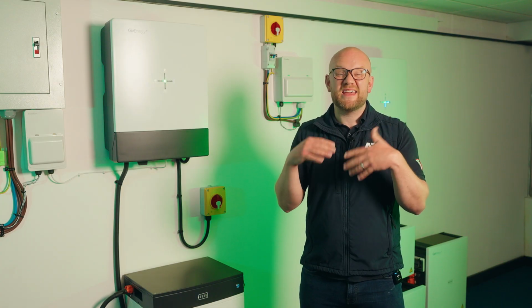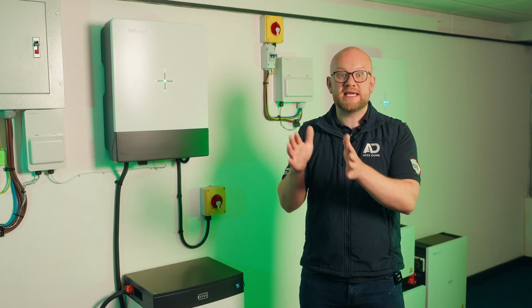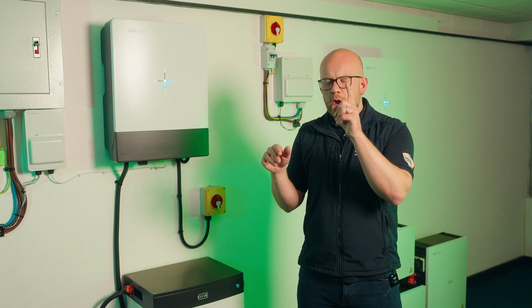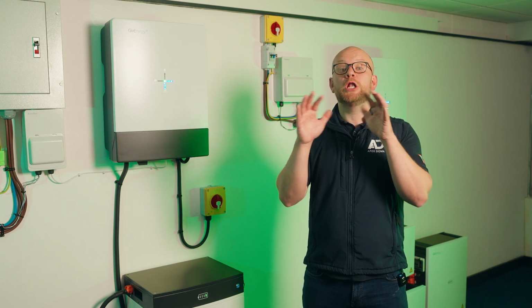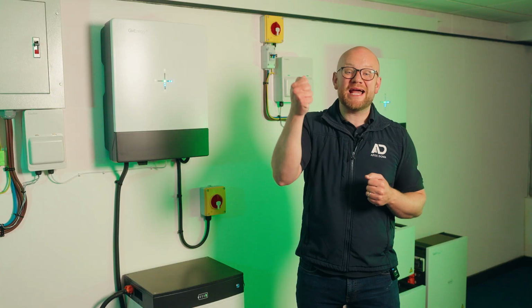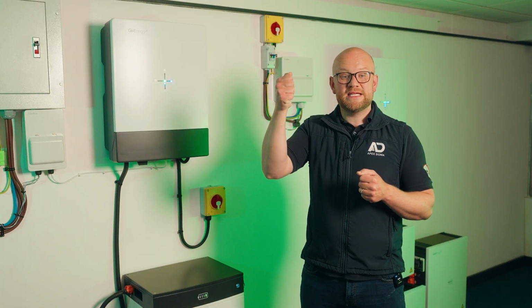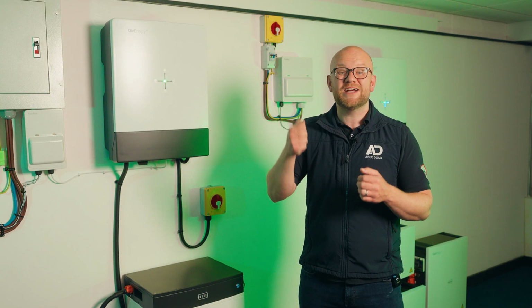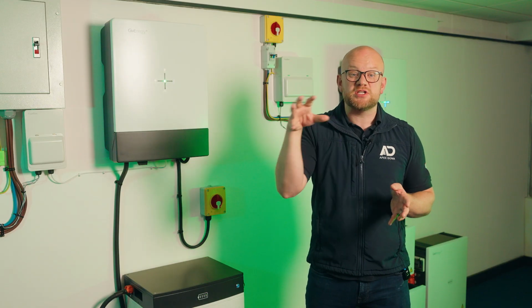Now, typically speaking, they'll give you at least 3.68 kilowatts onto the grid. But don't worry too much about this, because locally your inverter can still supply to your home at the maximum discharge rate of your actual inverter. So you've got a 10 kilowatt inverter, it can discharge its full amount. Then it's for your installer to essentially try and negotiate with the national grid to get the maximum rate of discharge out to the grid.